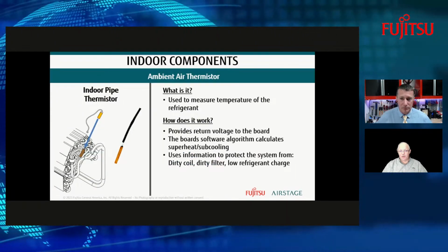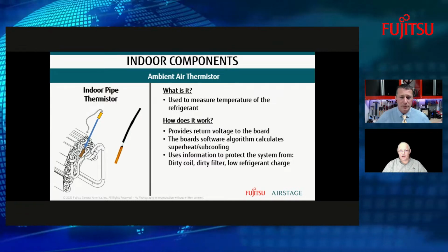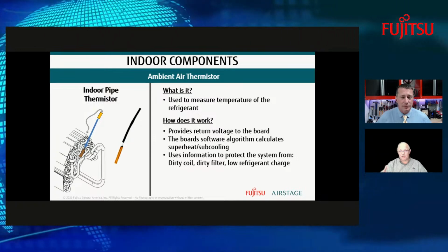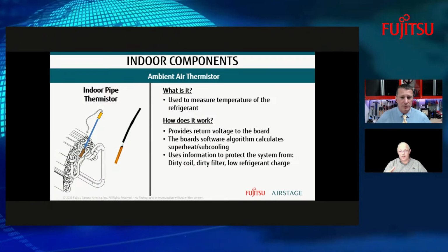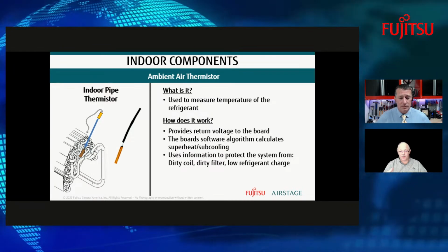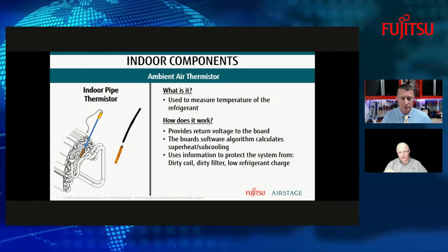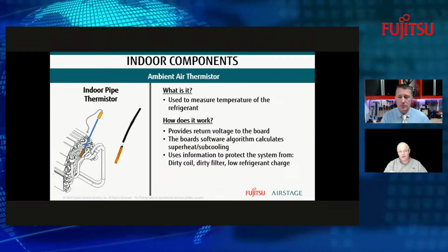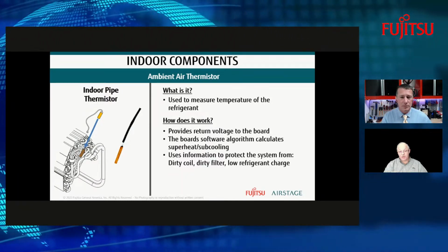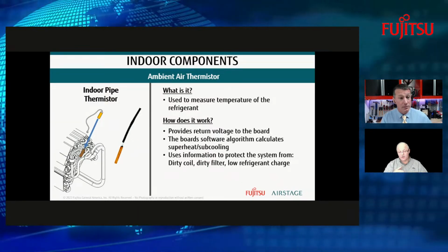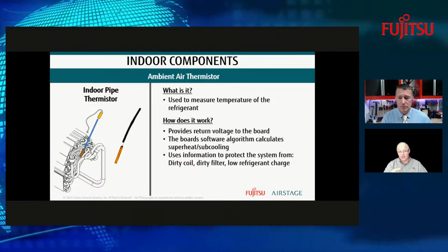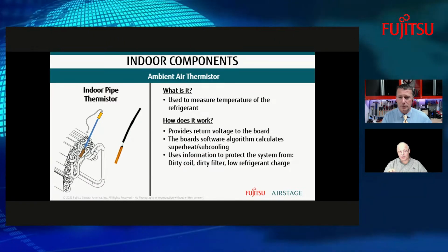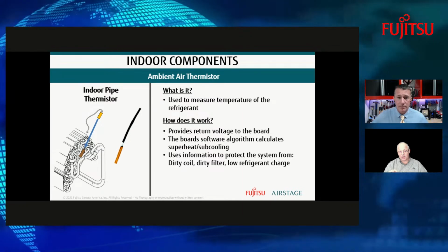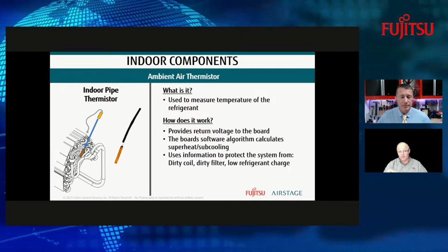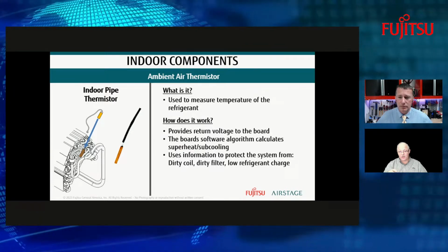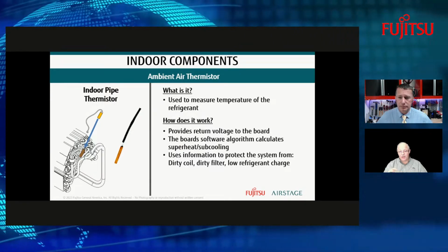All right, now we're still back at the indoor unit. So we've got an indoor pipe thermistor. That one's looking at the refrigerant flow, and again, it's sending back a return voltage. You can see how it slides down into that little bitty well right there. So it's looking at what's going on with the temperature. Now, the system could start doing some interesting things depending on whether that coil is clean. So if that coil inside gets dirty, you can see that we could have some capacity dropping because the system's trying to slow down because the line's getting too cold. So it's interesting how that is working in relation to superheat and subcooling.